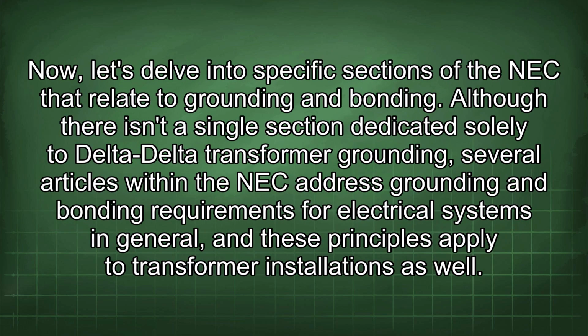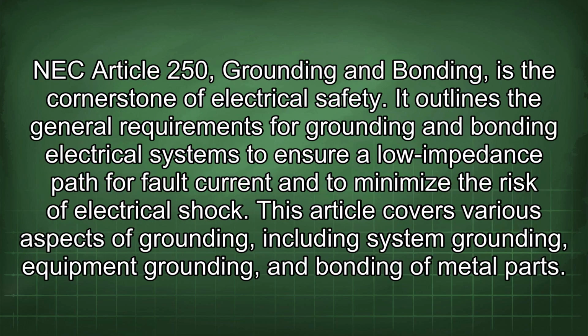Now let's delve into specific sections of the NEC that relate to grounding and bonding. Although there isn't a single section dedicated solely to delta-delta transformer grounding, several articles within the NEC address grounding and bonding requirements for electrical systems in general, and these principles apply to transformer installations as well. NEC Article 250, Grounding and Bonding, is the cornerstone of electrical safety. It outlines the general requirements for grounding and bonding electrical systems to ensure a low impedance path for fault current and to minimize the risk of electrical shock.